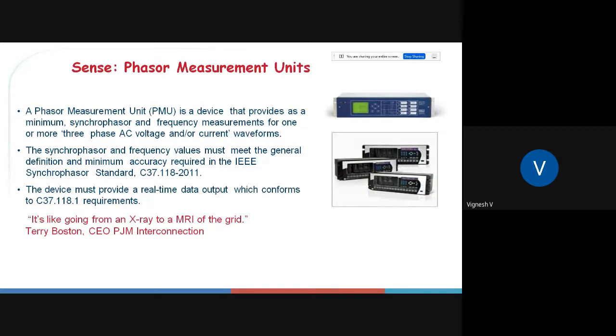C37.118.1 defines the PMU protocol mostly. So PMU is a device that provides you current phasors, voltage phasors, frequency measurements, rate of change of frequency for three-phase AC voltage and current waveform. So it converts the analog value to phasor - that's to put it in a very raw definition. It takes analog values from the CTs and PTs and gives you the phasor with reference to an absolute reference. It's not a relative reference, but an absolute reference, which is obtained from the GPS clock.